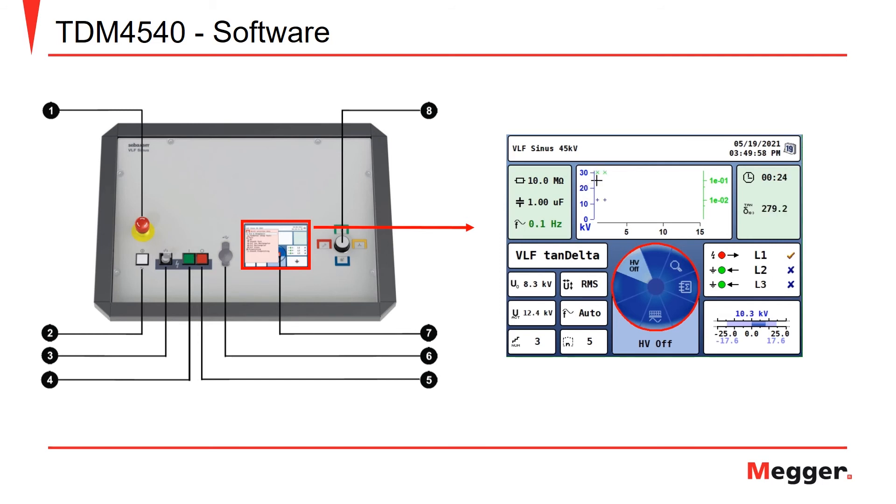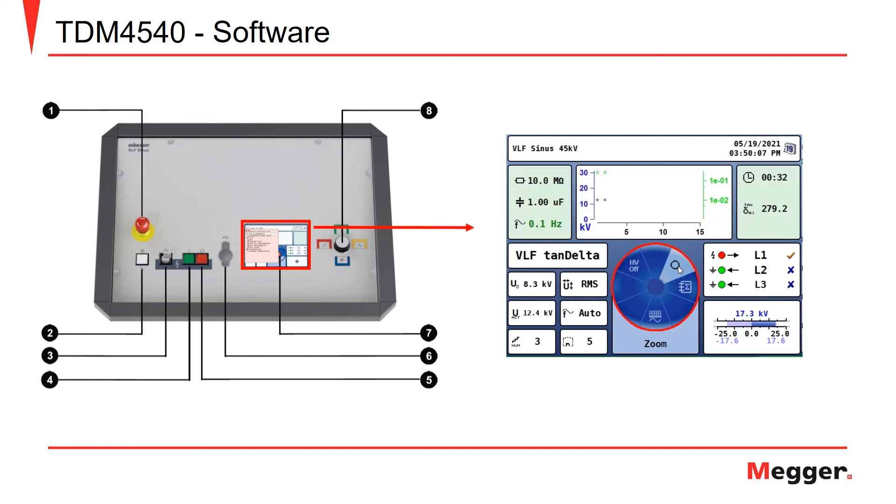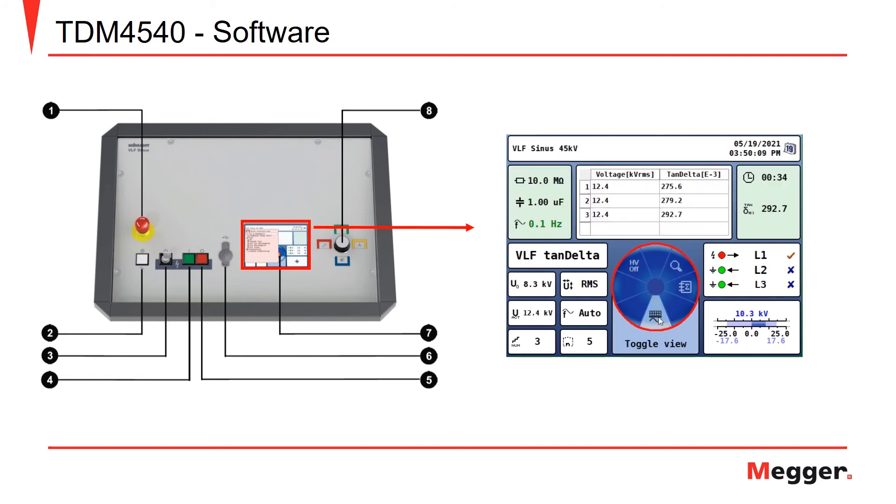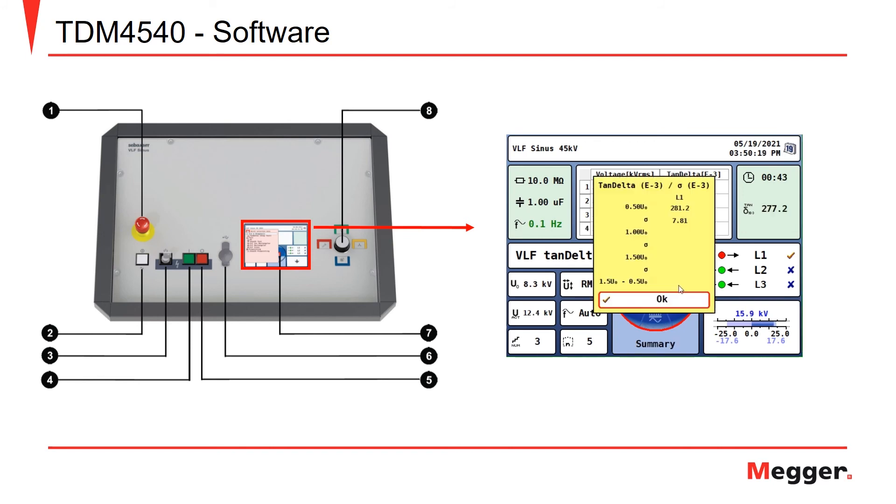Now we can go ahead and change the views if we wish. Here we have the applied voltage we can see. If we wish to change the view, we can have it in a table form that gives us the voltage in RMS and our tan delta value. And then we can actually look at a summary as well.